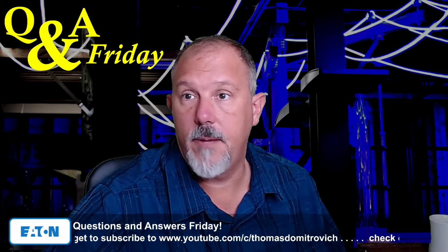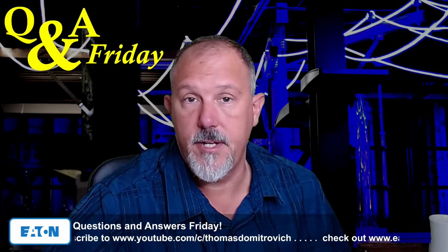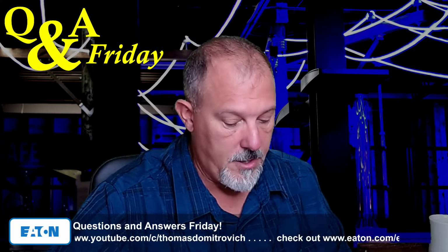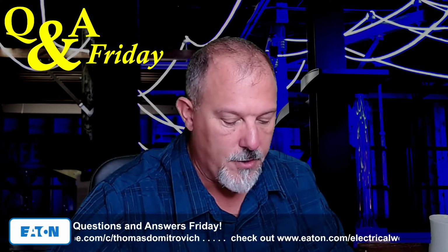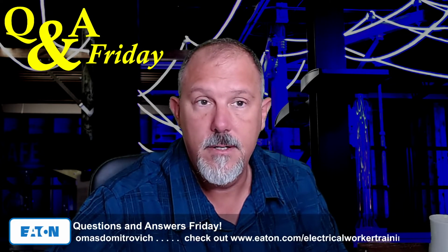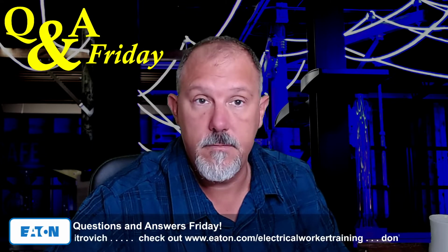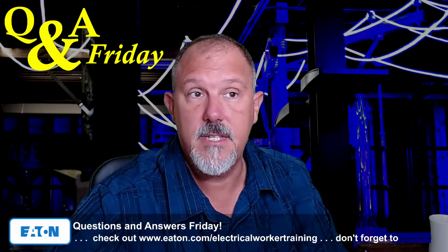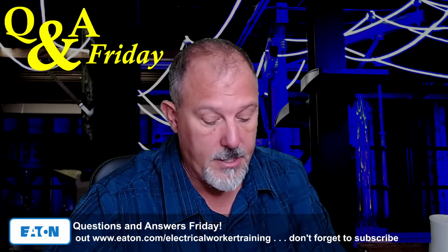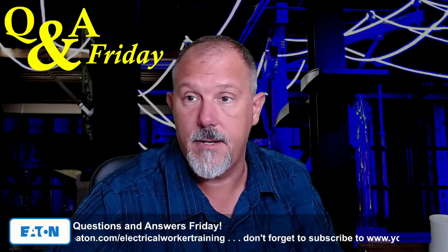I don't care if it's not providing overload protection. I don't care. It doesn't say that it has to. It just says it has to have an overcurrent device installed in the circuit breaker. It doesn't say you have to use overcurrent. It doesn't say it has to be set any particular setting. It just says if it's 1200 amps or higher.